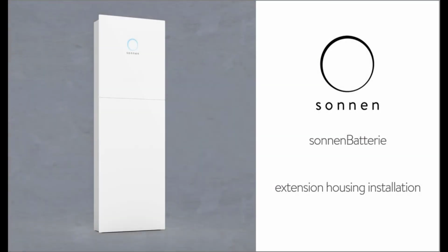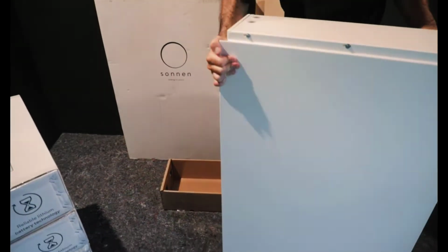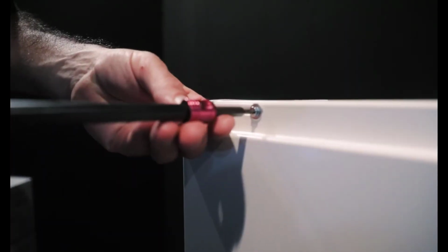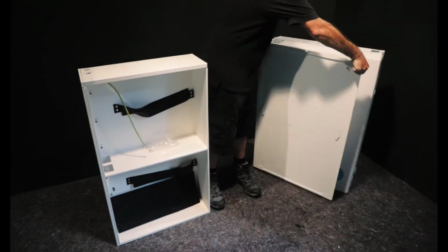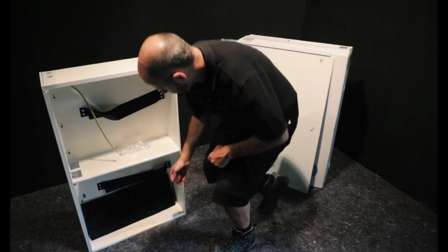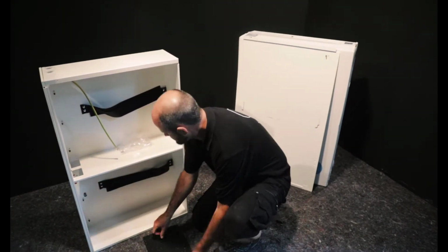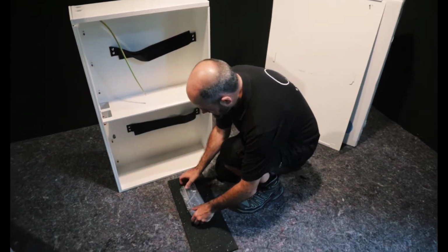We then get to install the extension housing itself. So these aren't always typically used. If you've got a system that's only got the two battery modules, you don't need to use this, but if you've got a larger system you can, or if you're going to install the system to add battery modules later on, you use this. So first thing we do is to take the front cover off, simple 3 little screws, take out all the little accessories which were inside it, and then position it back to the wall.